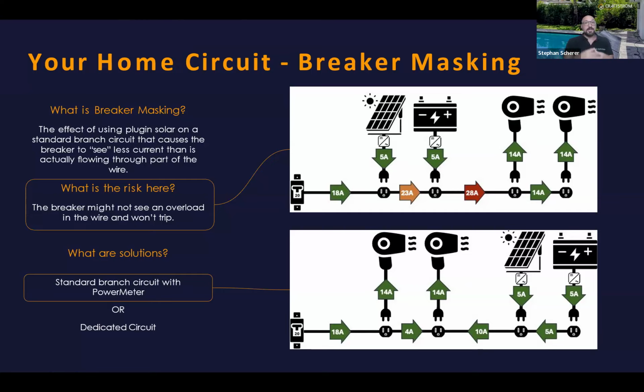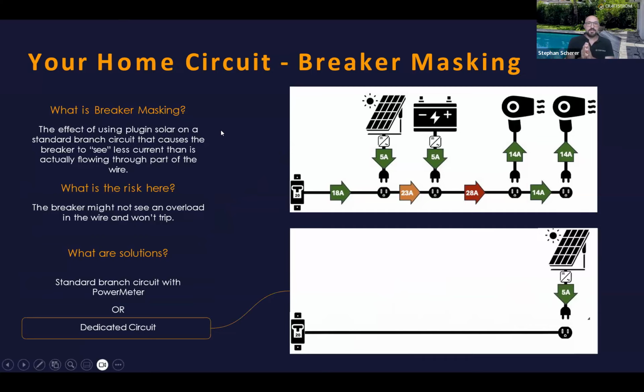That information is then reported to, for instance, the inverters. And there's a very simple algorithm that ensures that the total power that you're using plus total power that you're producing together, summarized, do not overload the circuit. So that means, in essence, you might have to reduce your solar output to ensure that you cannot overload your circuit. That's what the NEC wants. Or, and if you could please get to the next slide, you have a dedicated circuit.